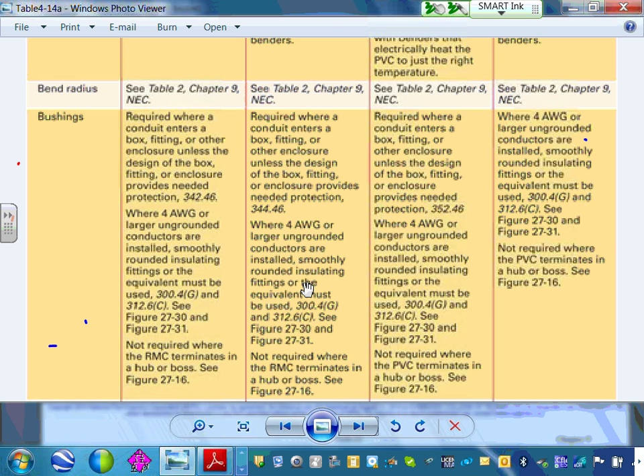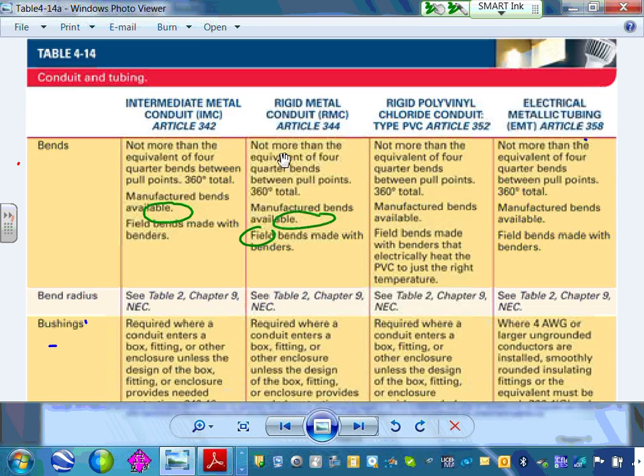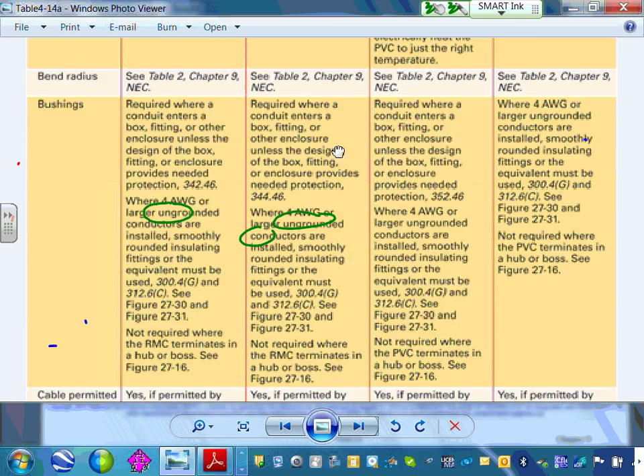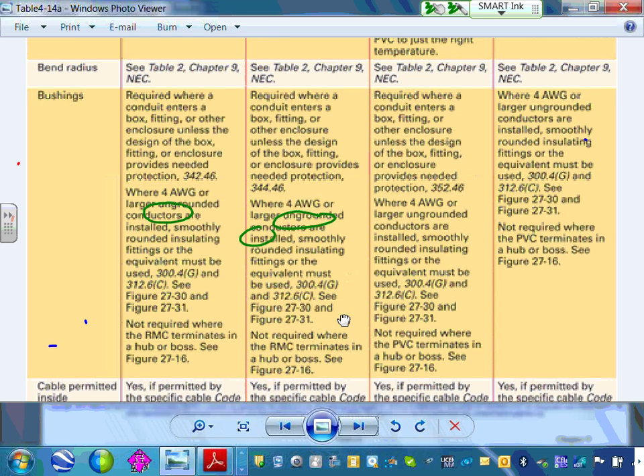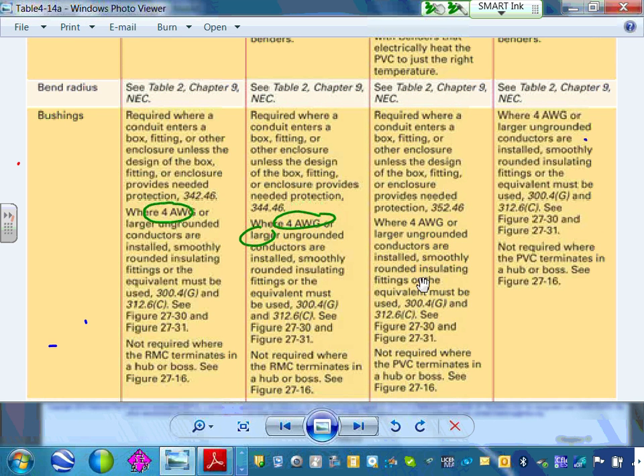Bushings, guys, are required where number 4 or larger conductors are used. These are required where a conduit enters a box or fitting. The first ones, these are rigid metallic, number 4 or larger. Typically, all of them are number 4 or larger. You're required to put bushings in all of them. Number 4 or larger bushings are required where the conduit enters the fittings or the box.